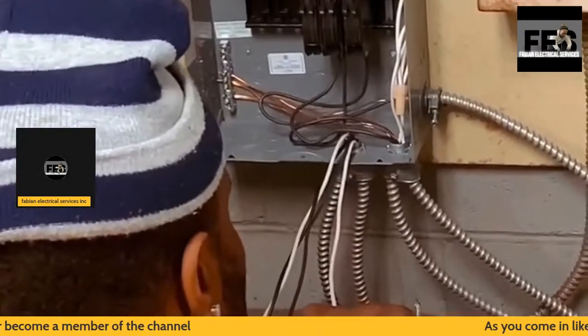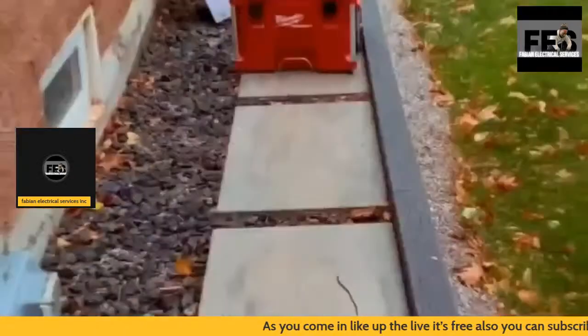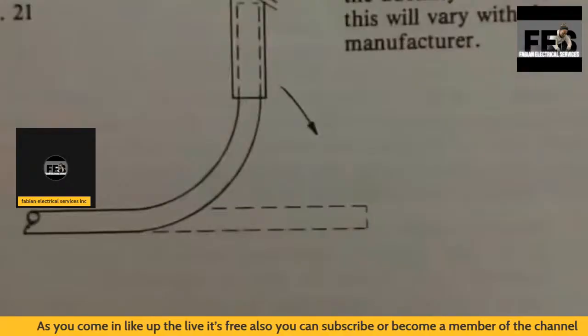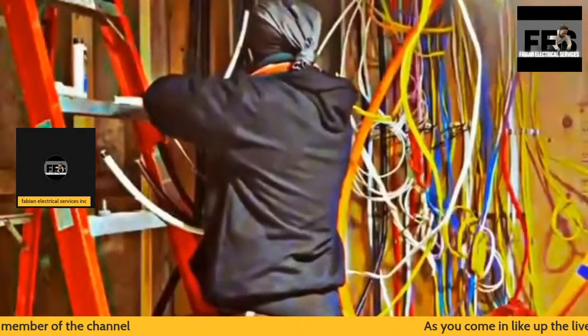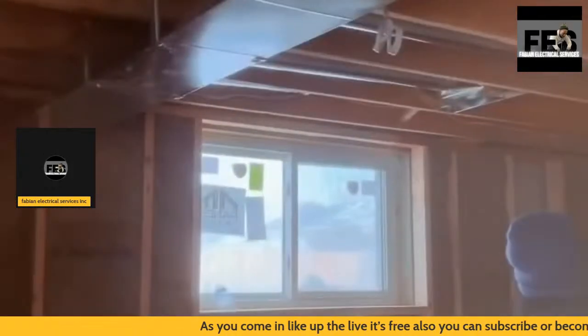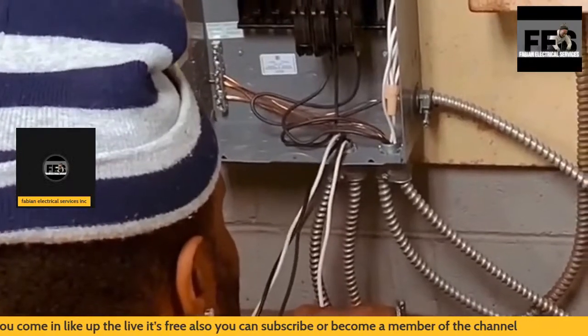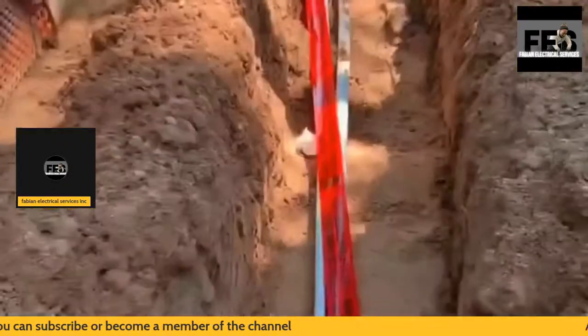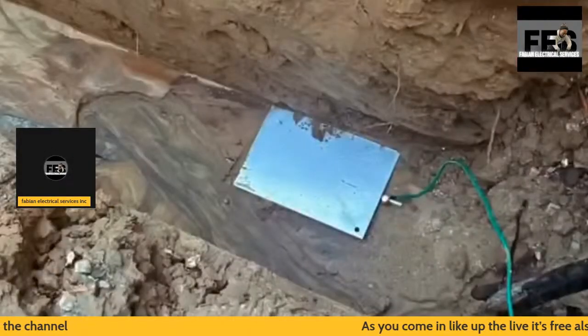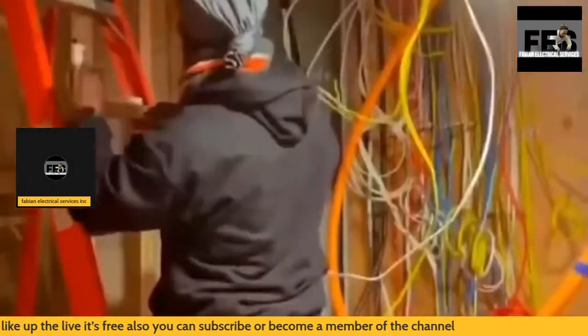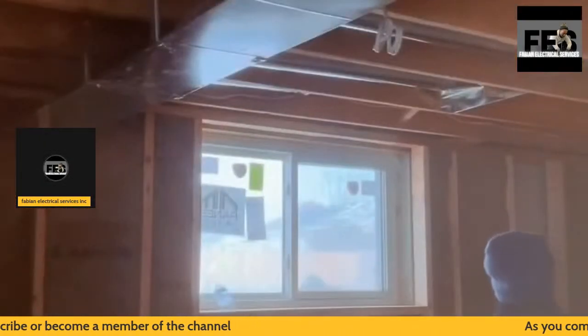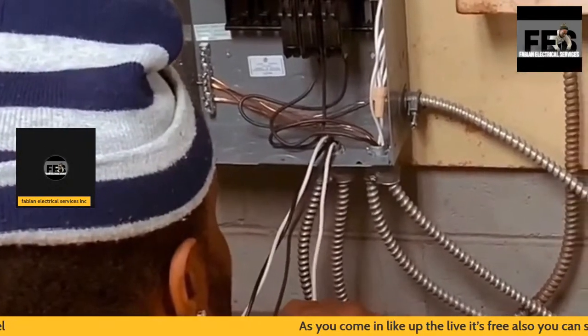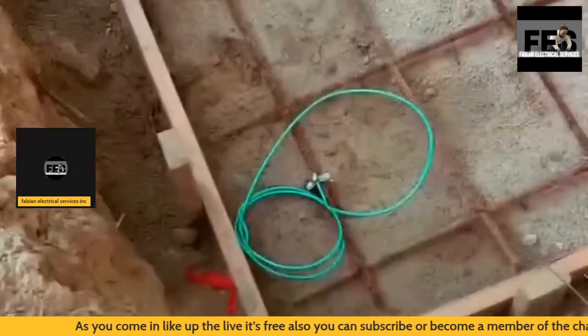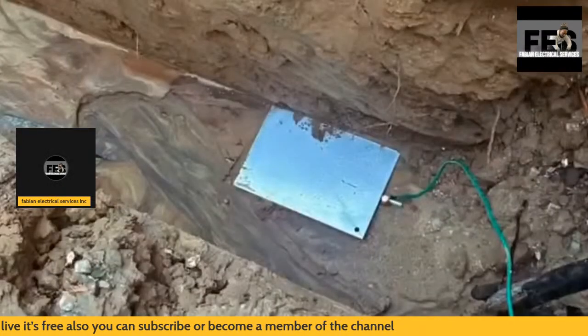The previous video was of me doing an installation of a 400 amp panel located in the basement of the home, with parallel feeds run to pick up the actual 400 amp panel. The breaker at the panel is a special type of breaker, I've opened one up in a previous video showing the blades and mechanism inside. It is a 400 amp main service that was installed, using Teck cable, the trade name we normally use, and the service was entered from the top of the panel.